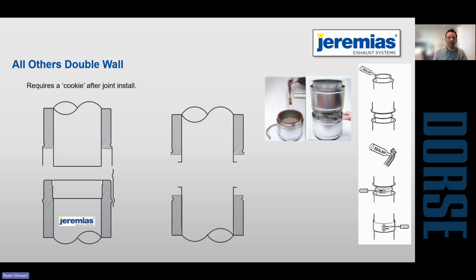One of the other benefits is all the insulation is on the inside here, so none of it's exposed during duct cleaning. And you don't have any sealant leaking out, whereas with this one, when you're putting it together, a lot of it pushes out. Some of it pushes into the ductwork, and over time, some of that sealant's going to be washed away, so you'd be more likely to have leaks with something like that. Feedback on the Jeremias stuff, at least up to the 18 or 20 inch size, is that it's much quicker to install. So they see up to 50% savings in installation.